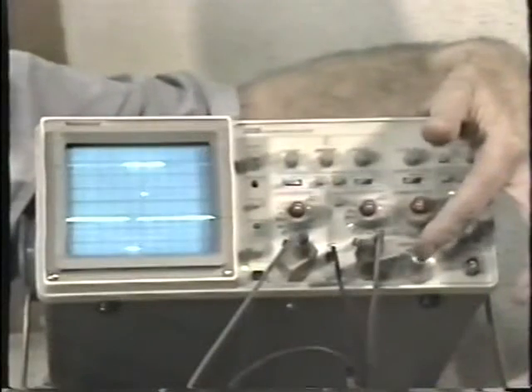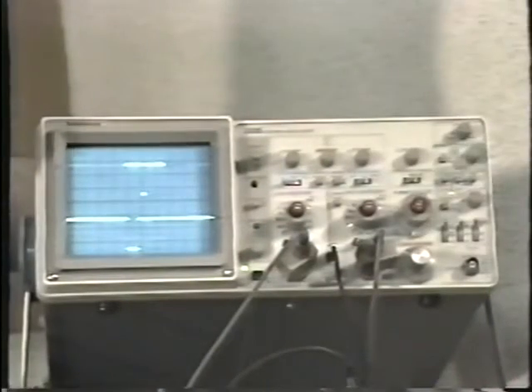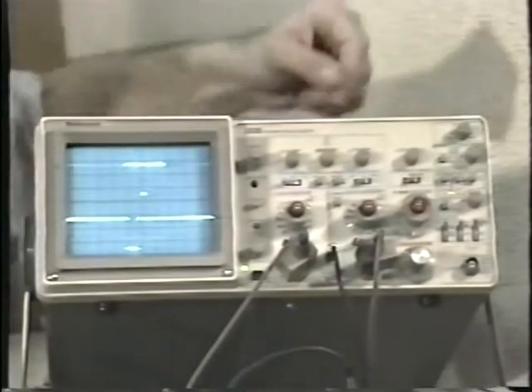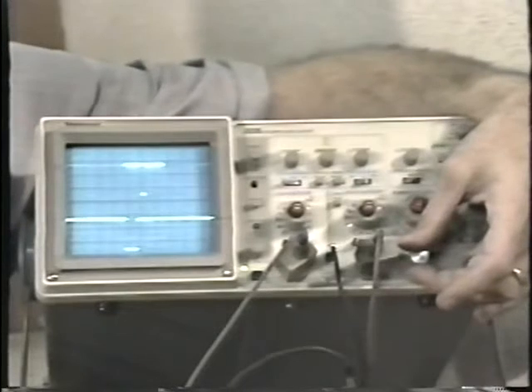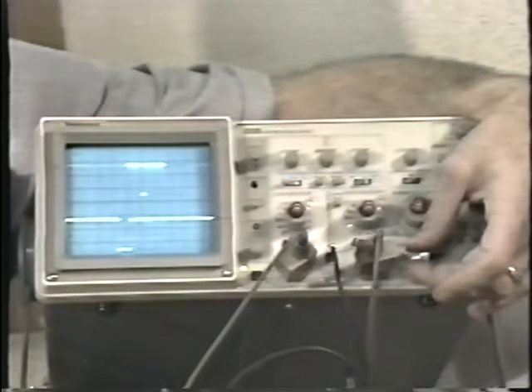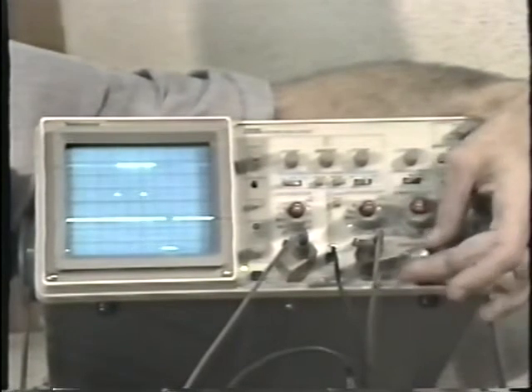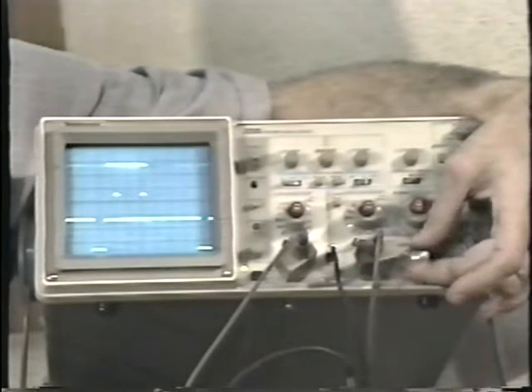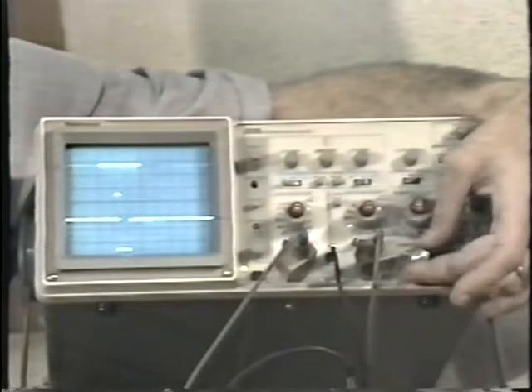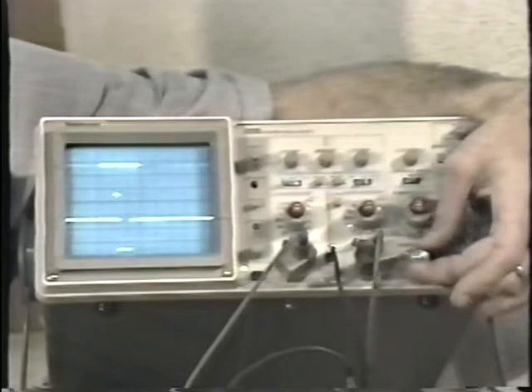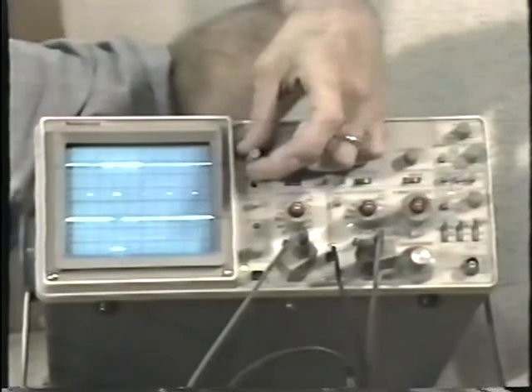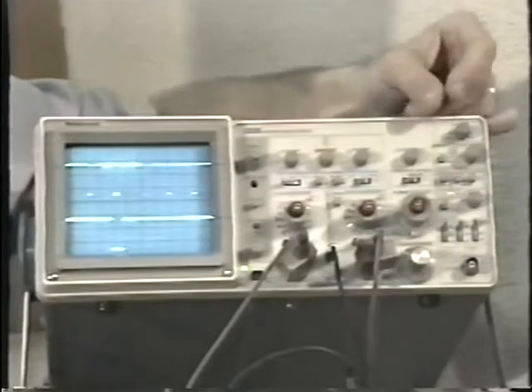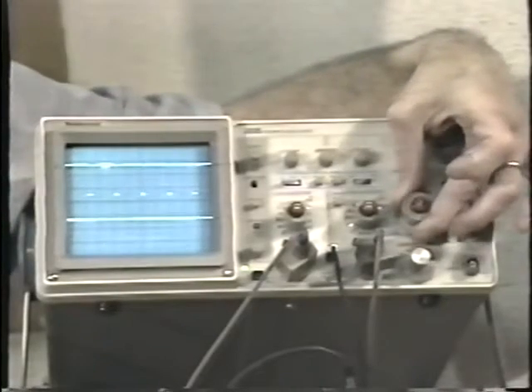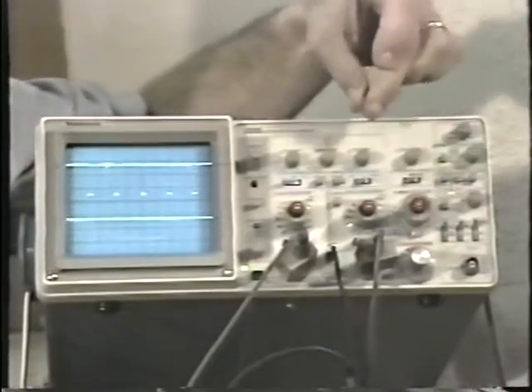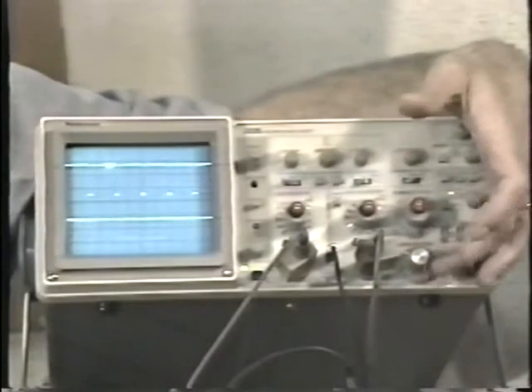Not only that, I can select where on the A sweep I'm going to expand it. This control is known as the vernier, and what it really is is a multi-turn potentiometer. Watch what happens as I adjust the vernier control for the B delayed sweep. I can adjust where on the A waveform the B sweep picks up and ends. Let me turn up the brightness a little bit more. Remember, that's what the waveform looks like. In fact, I can select a very small portion for the B sweep and display that.